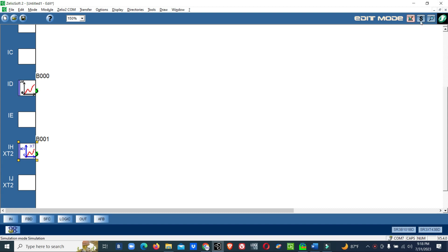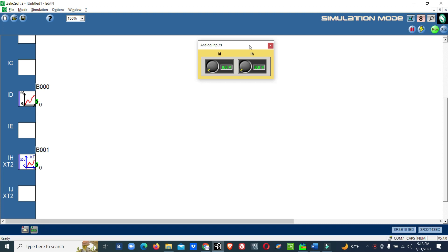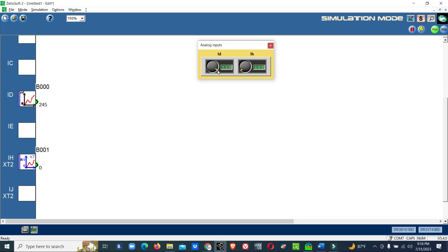Now I am increasing the 8-bit analog input from zero to full value. At zero volts, you can see the value is zero. At 9.9 volts — close to 10 volts — it is showing 255. So the 8-bit analog input goes from 0 to 255. From the field, 0 to 10 volts is given to the PLC. The PLC receives the voltage as bits from 0 to 255, and that binary input is converted to the decimal value.